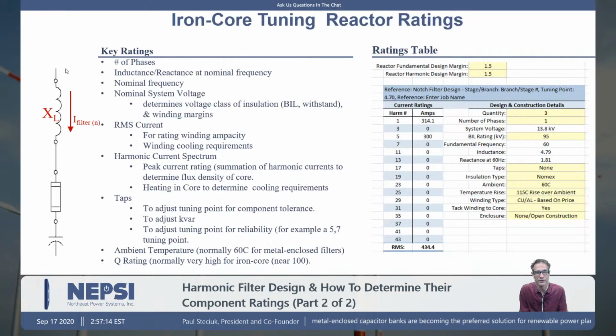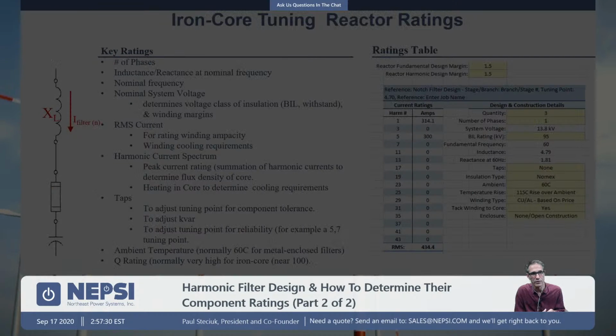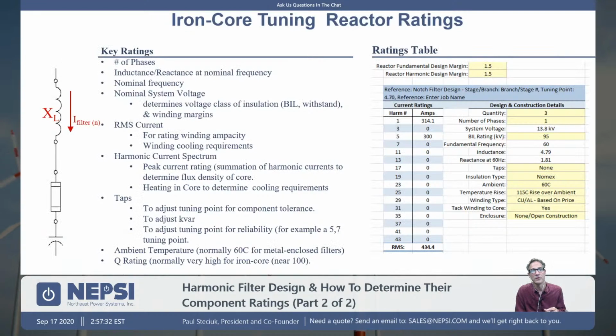And really, this helps to guarantee that you get the 250% linearity that we recommend. It also allows for the reactor to run quieter. It gives it less losses. And it helps to give you a much higher reliability. So putting a 1.5 multiplier on the harmonic filter and on those harmonic filter reactors will result in a much higher reliable design. But it costs more.